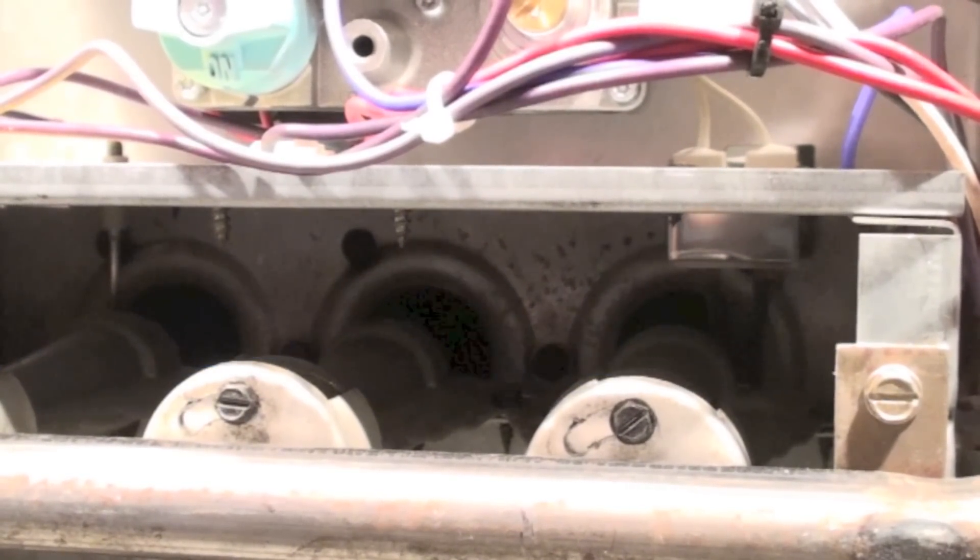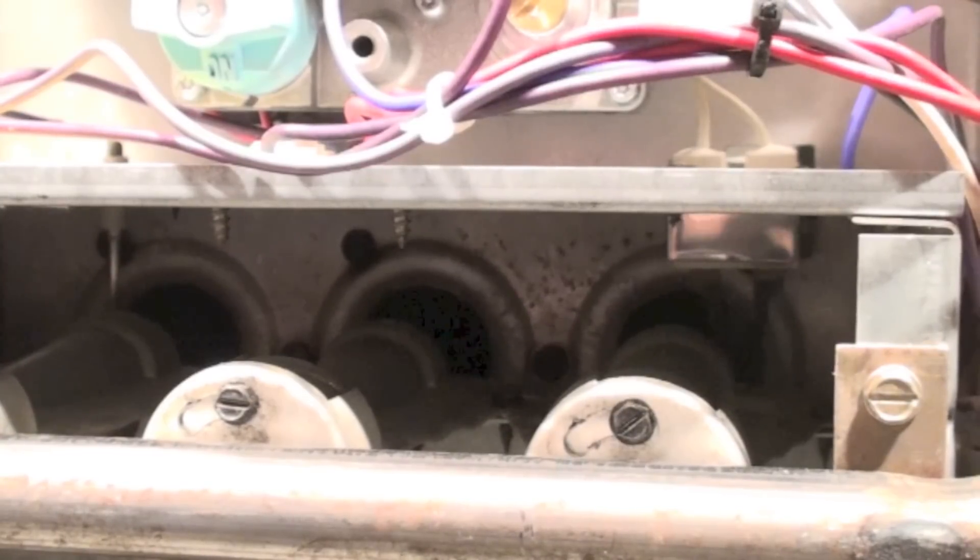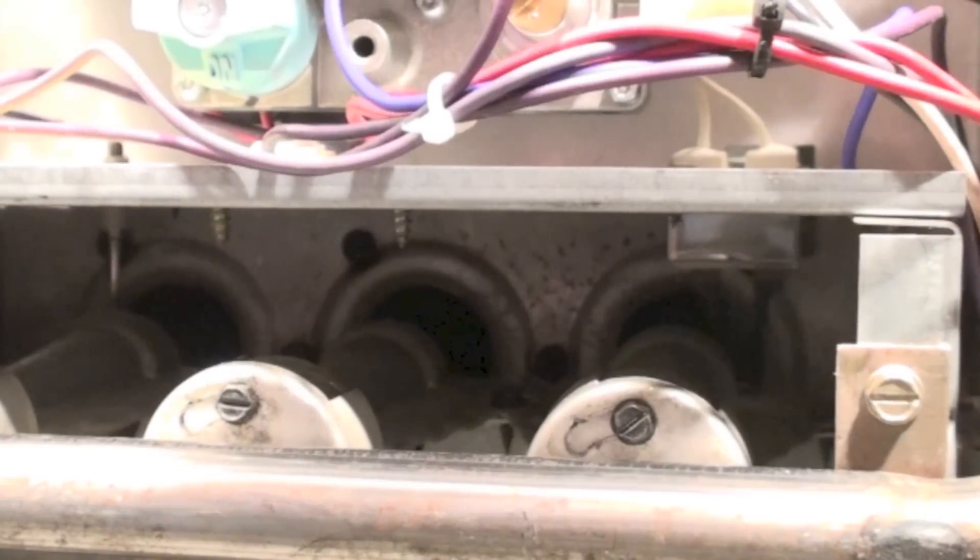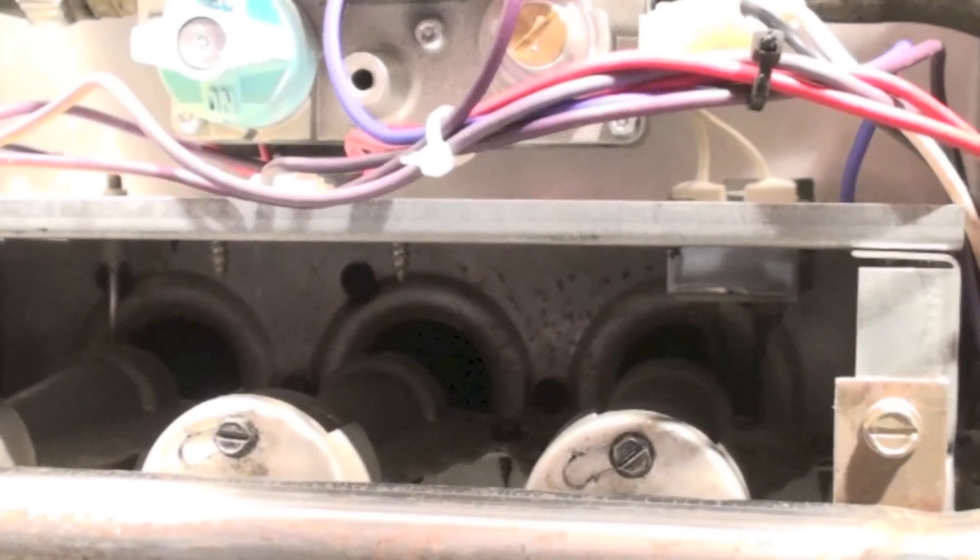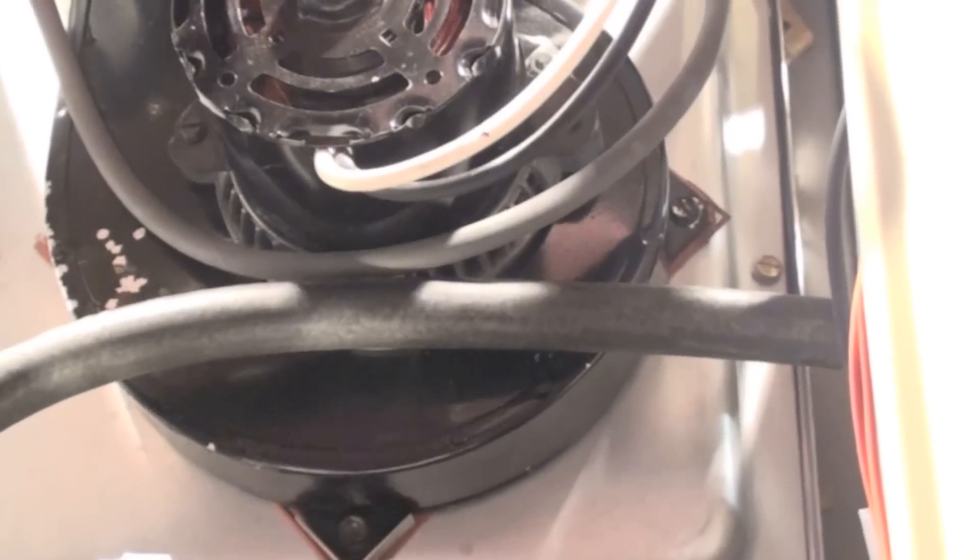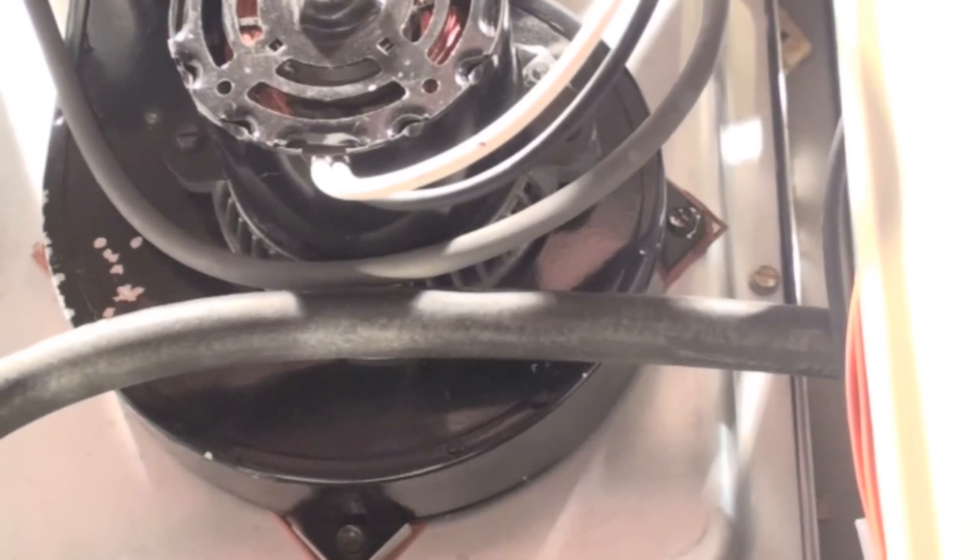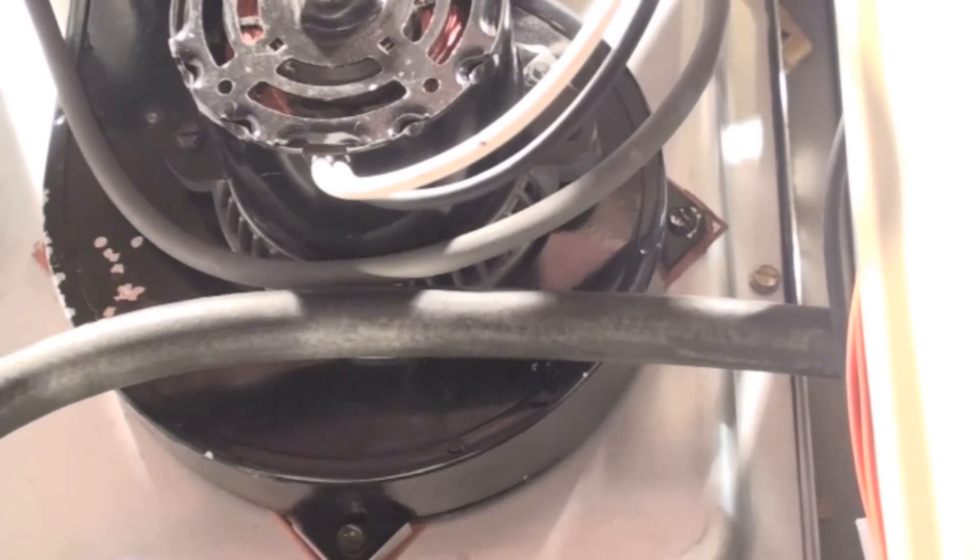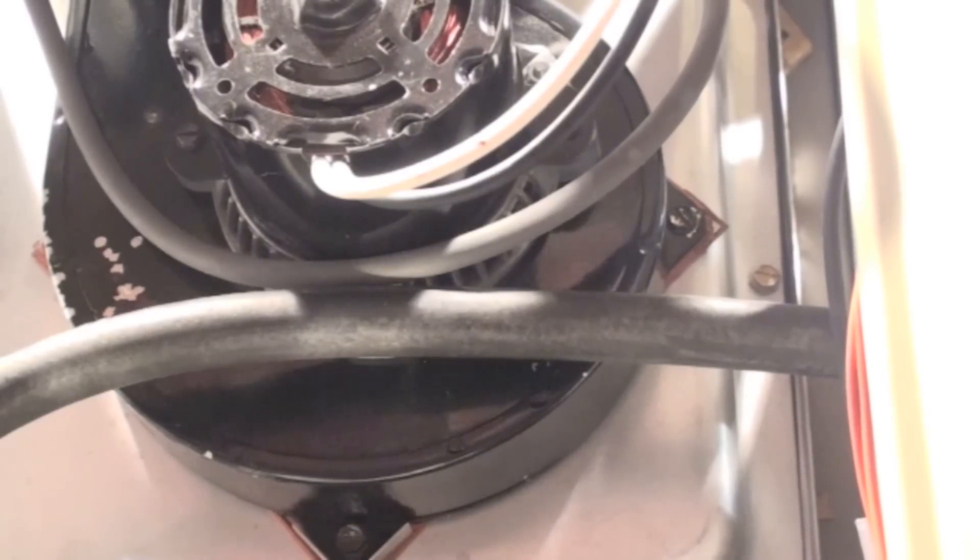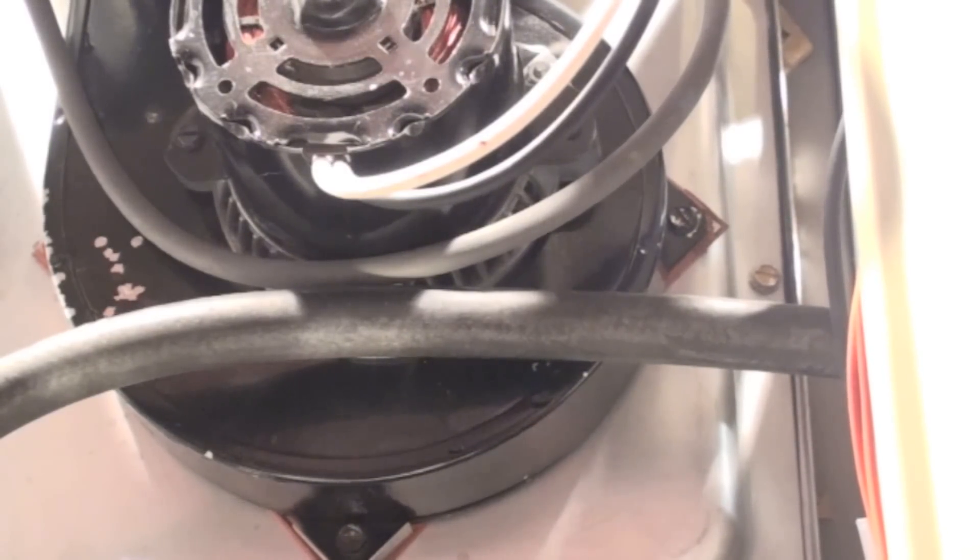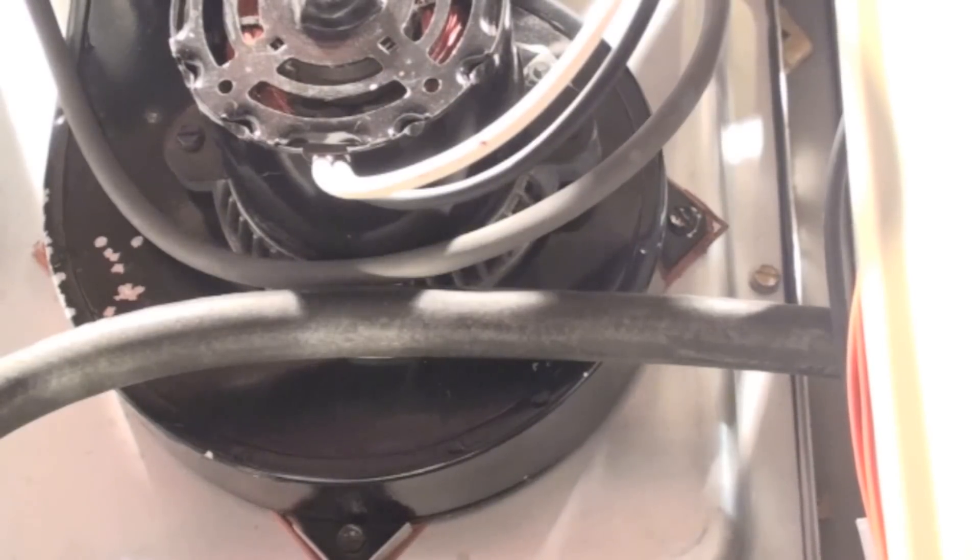The burner immediately goes off. The inducer is still running, still rotating. It goes for about 30 seconds after the burner shuts off. The blower will run anywhere from a minute and a half to two and a half minutes after the burner shuts off.